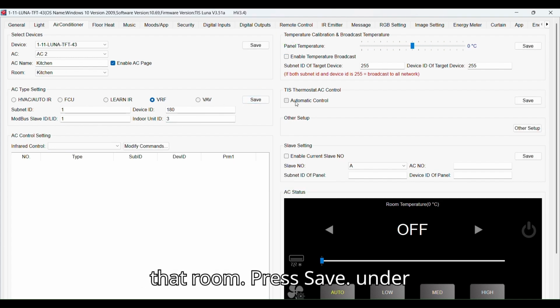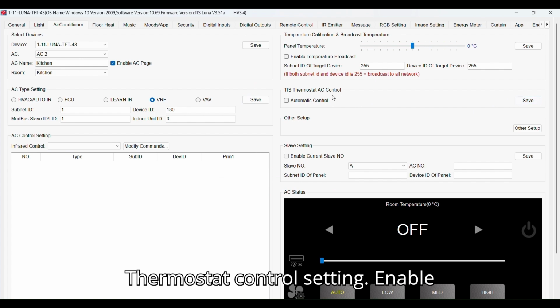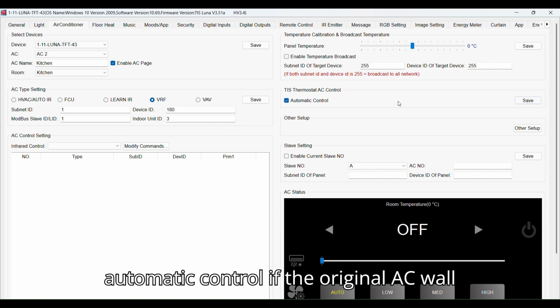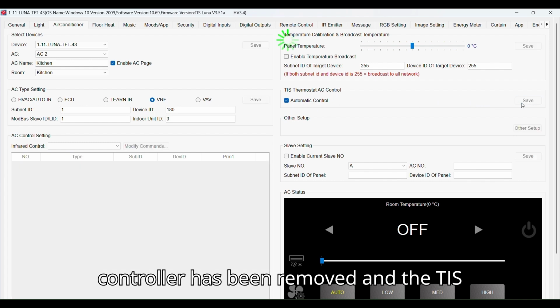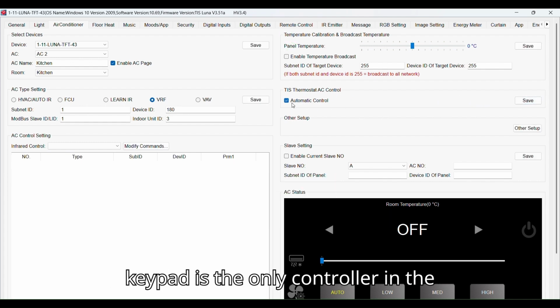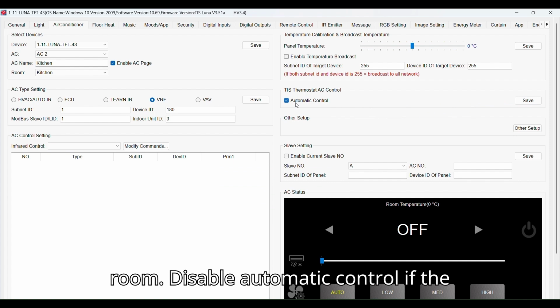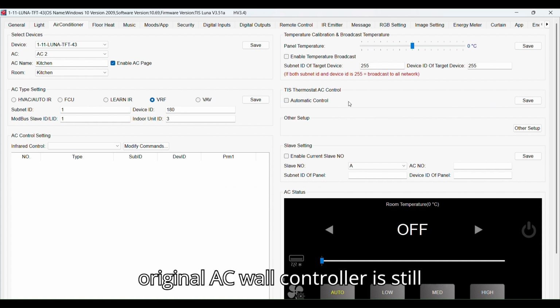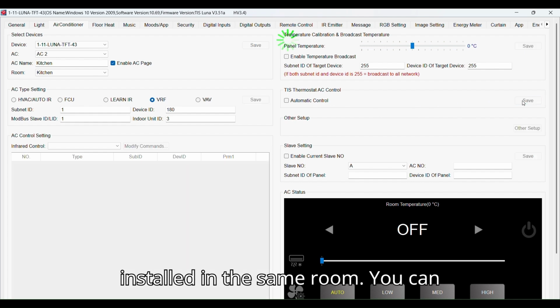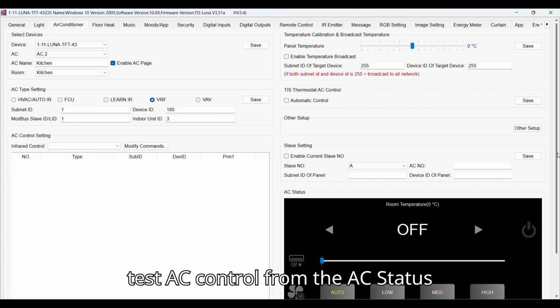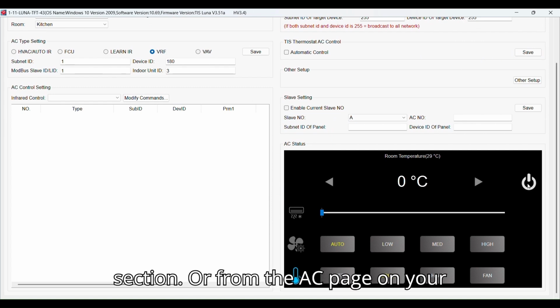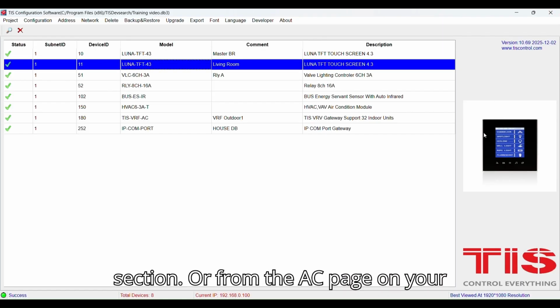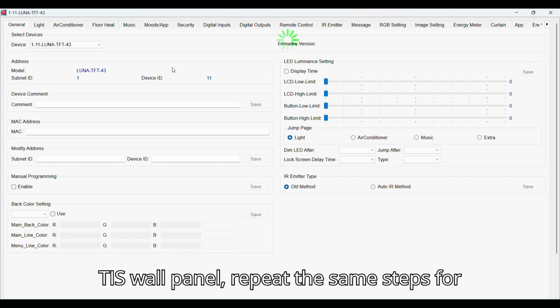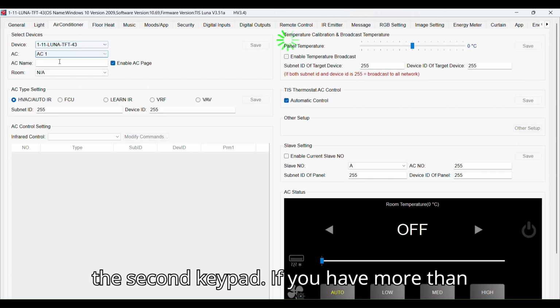Press Save. Under Thermostat Control Setting, enable automatic control if the original AC wall controller has been removed and the TIS keypad is the only controller in the room. Disable automatic control if the original AC wall controller is still installed in the same room. You can test AC control from the AC status section or from the AC page on your TIS wall panel. Repeat the same steps for the second keypad.